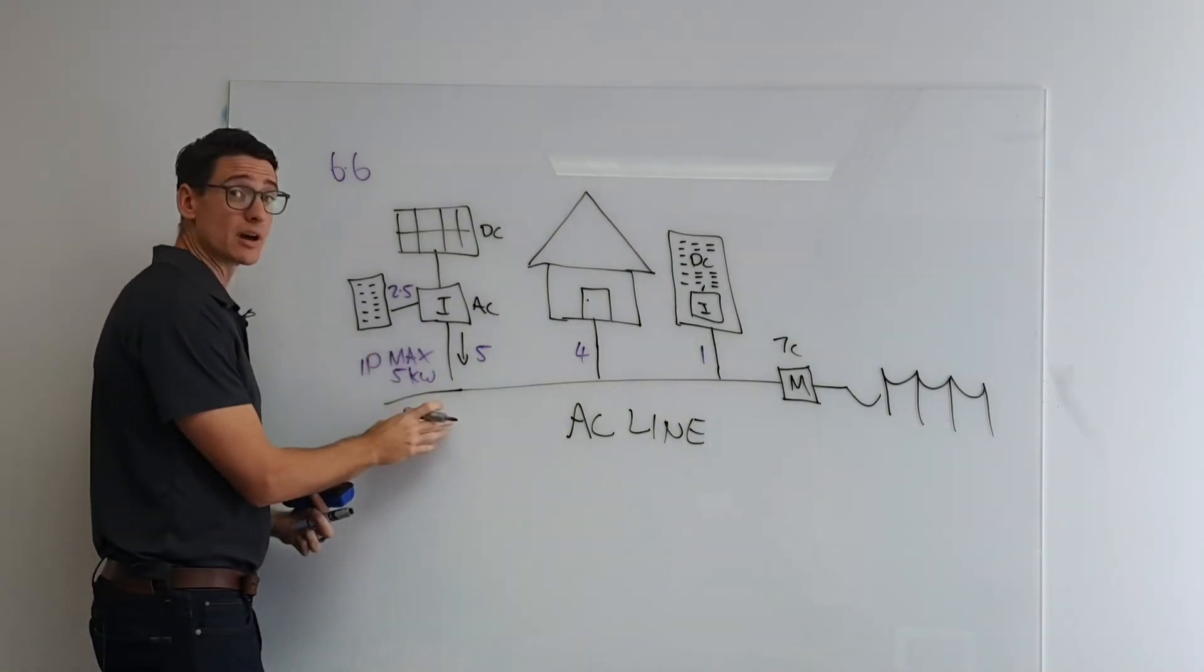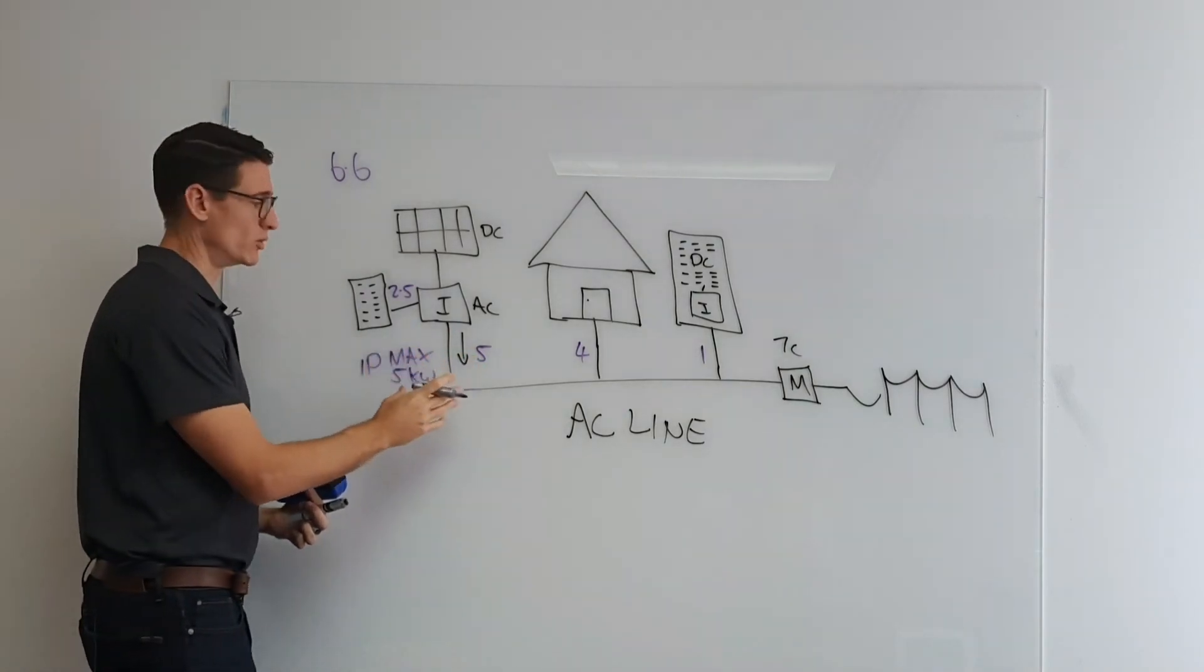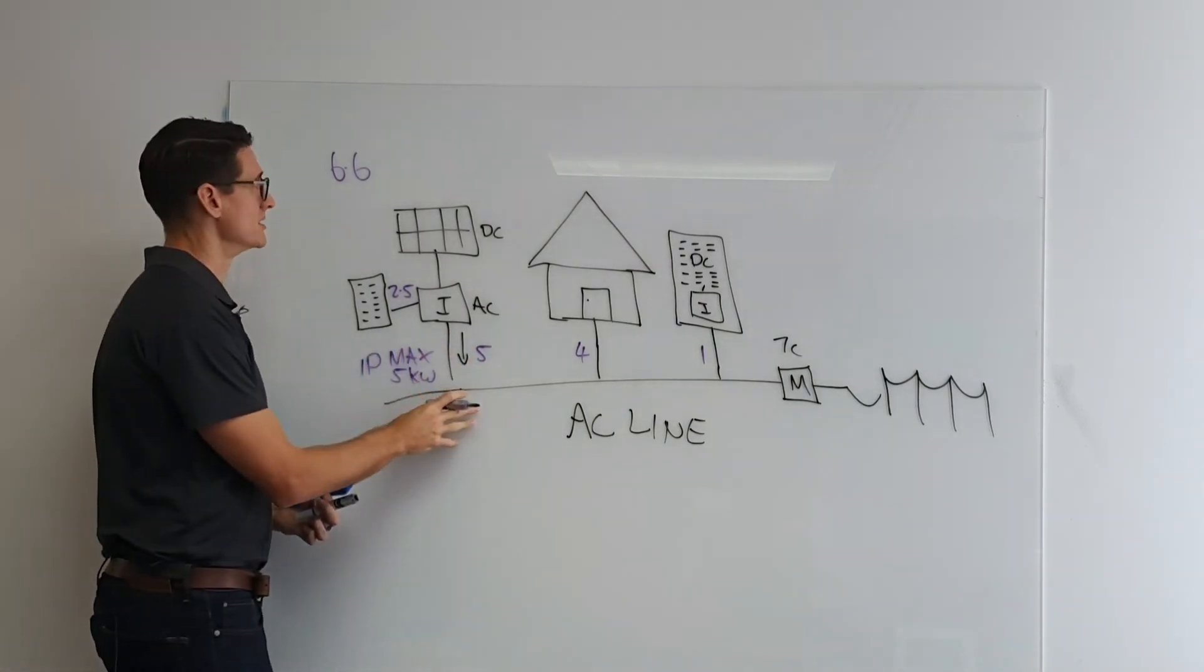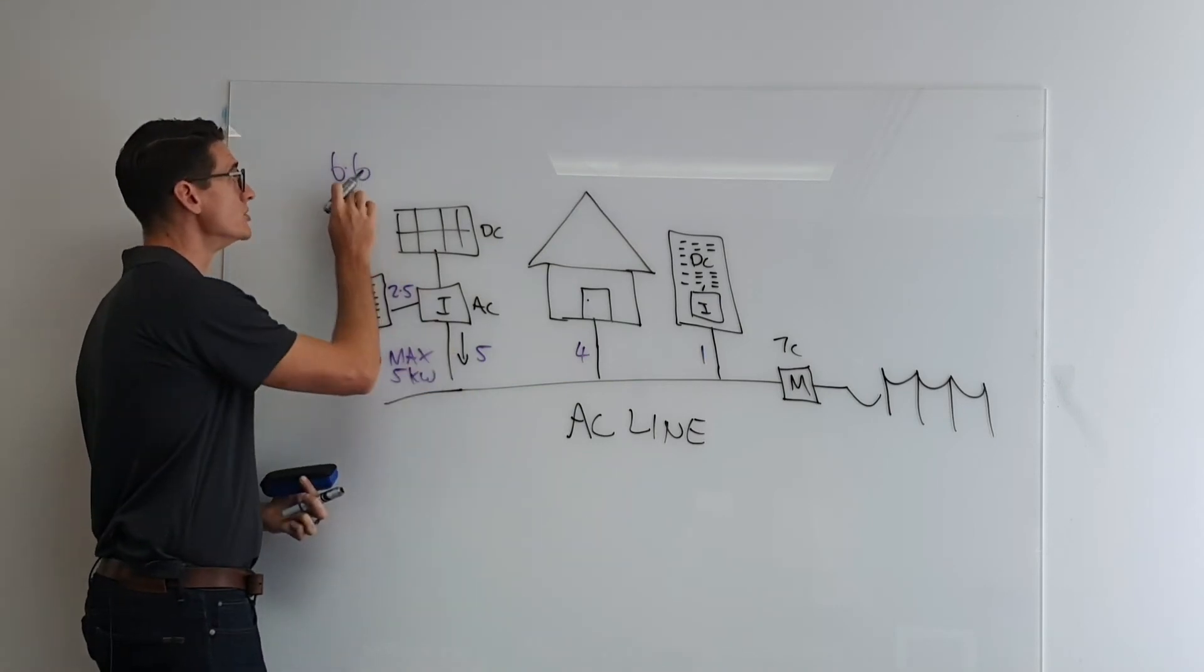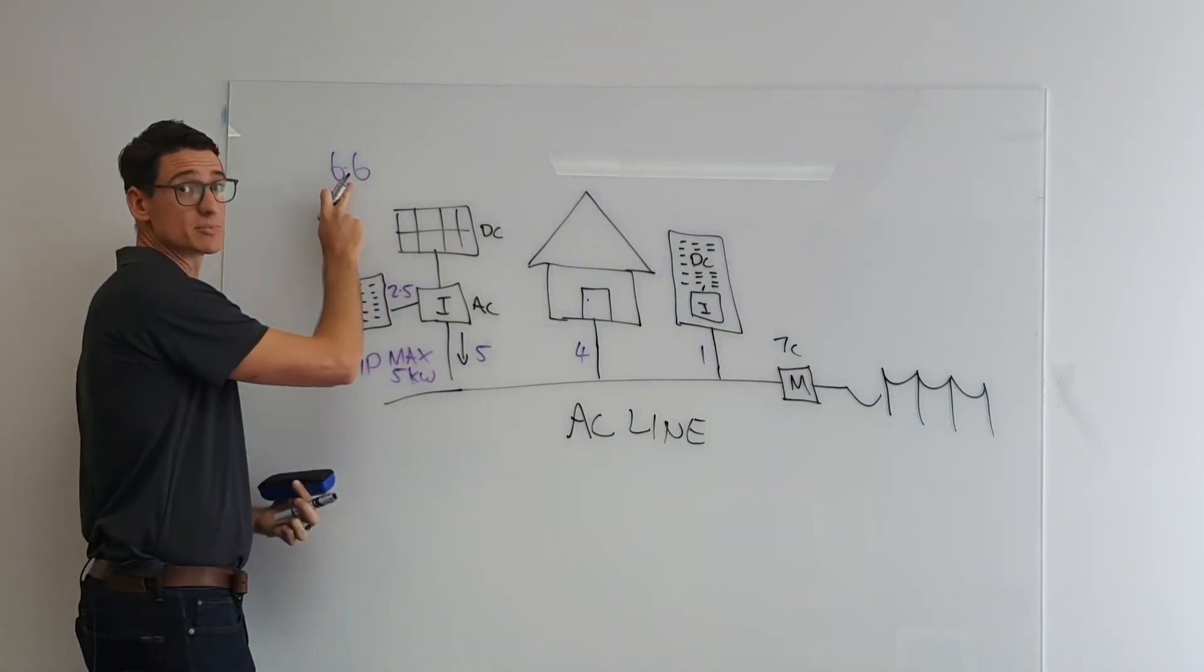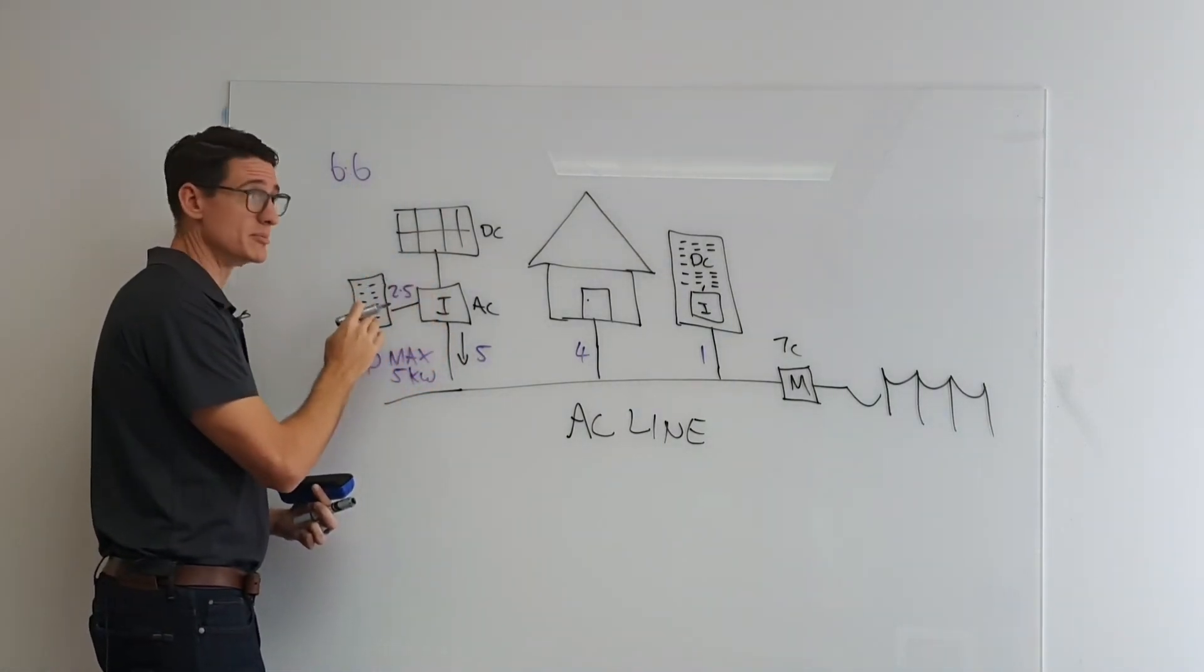With a hybrid type system, what you're actually allowed to do, and this is different, this is more around STC calculation, again, perhaps another video, is that you're actually allowed to install more than 6.6 kilowatts worth of panels on a 5 kilowatt inverter, if it is a hybrid, it has this DC charging capability.